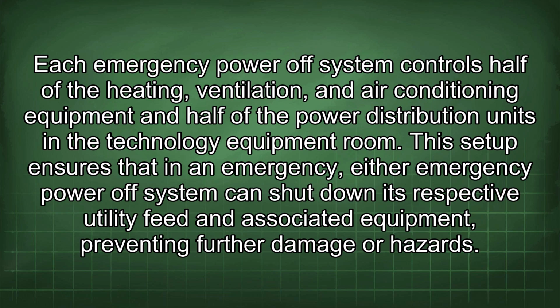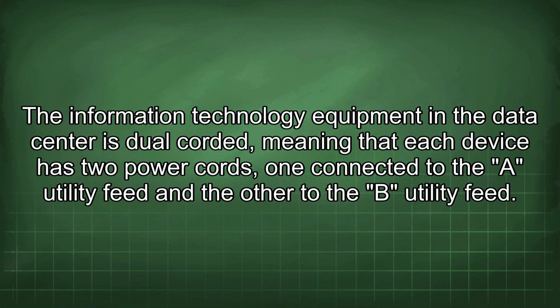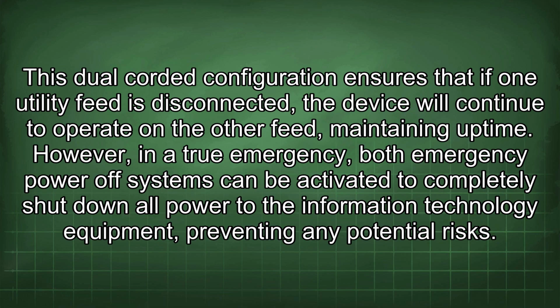Each emergency power-off system controls half of the heating, ventilation, and air conditioning equipment and half of the power distribution units in the technology equipment room. This setup ensures that in an emergency, either emergency power-off system can shut down its respective utility feed and associated equipment, preventing further damage or hazards. The information technology equipment in the data center is dual-corded, meaning that each device has two power cords, one connected to the A utility feed and the other to the B utility feed. This dual-corded configuration ensures that if one utility feed is disconnected, the device will continue to operate on the other feed, maintaining uptime. However, in a true emergency, both emergency power-off systems can be activated to completely shut down all power to the information technology equipment, preventing any potential risks.